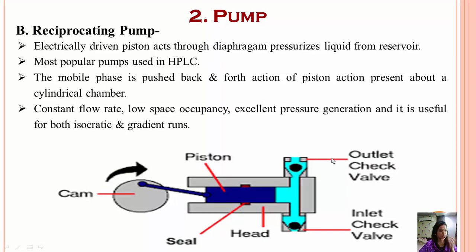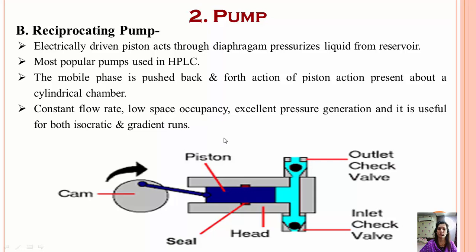The second pump available is the reciprocating pump, which is an electrically driven pump that acts through a diaphragm. You electrically apply pressure, and through the diaphragm it acts on the outlet and inlet valves. The inlet valve connects to the mobile reservoir where the solvent comes from, and the outlet connects to the HPLC column. A constant flow is achieved by the back-and-forth action of the piston through the diaphragm. It is very compact, generates excellent pressure, and is applicable for both isocratic and gradient runs.